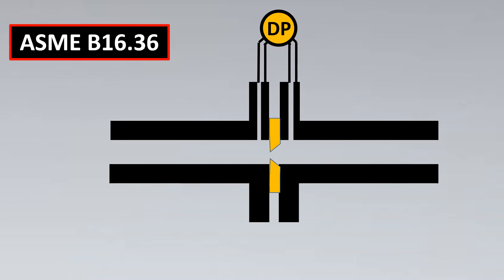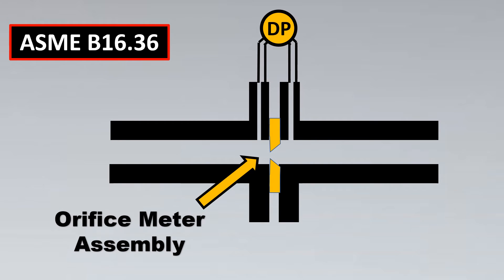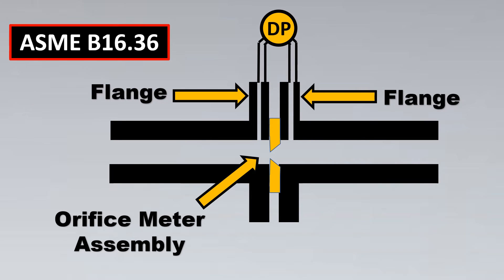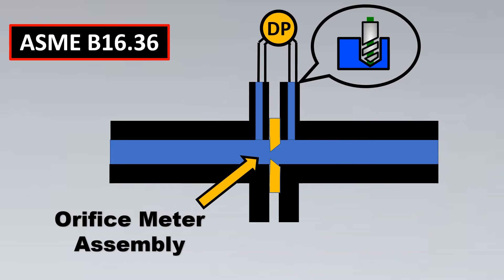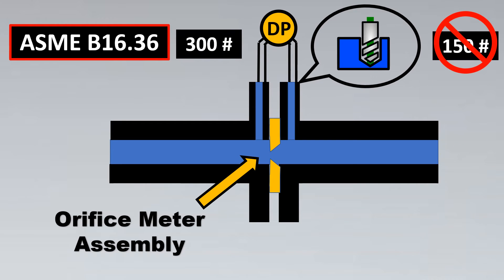Now let's look at the most interesting part: ASME B16.36, used for orifice meter assemblies. Orifice flanges are a little different from regular flanges because the liquid flowing through has to be measured when a differential pressure is created. These flanges have to be physically drilled, and when you drill a flange you reduce its mechanical integrity by putting a hole through it. Because of this, 150 pound rating is not part of B16.36 — it starts directly from 300 pound rating, as these flanges are specially designed to accommodate such drilling.